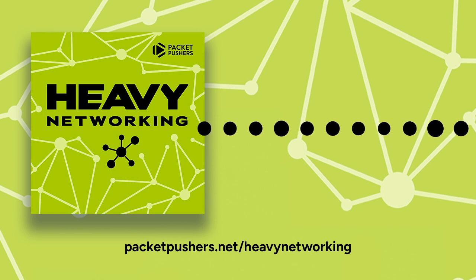But it has to be designed so that if it starts to get big, they design the broadcast distribution table to not go everywhere, but to go to a central hub BBMD and only send it out to spokes that are really interested or should hear that broadcast. Scoring special points if you accidentally have two BBMDs on the same subnet, you might cause a loop and melt the whole thing down.